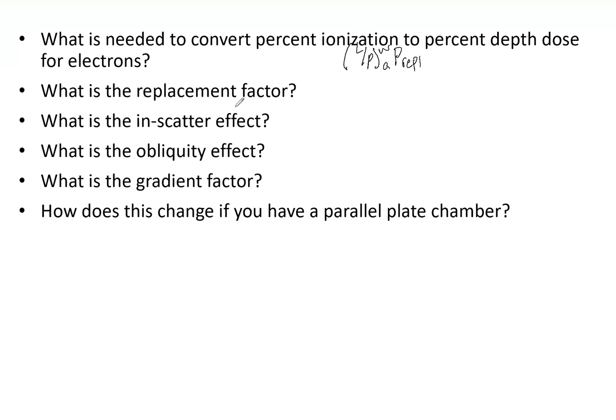You would find your percent ionization number, multiply it by these two, and that is how you would get percent depth dose. Also remember that clinically, normally there is very little difference, so percent ionization for the most part we can assume is percent depth dose.